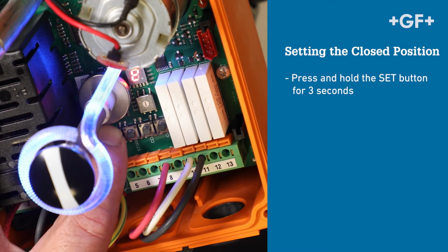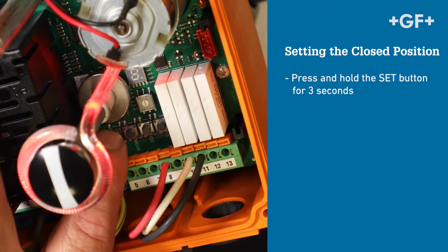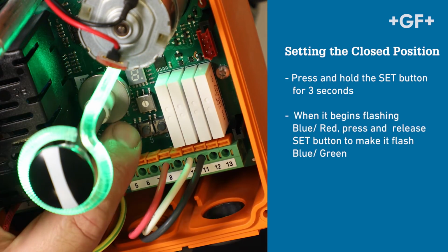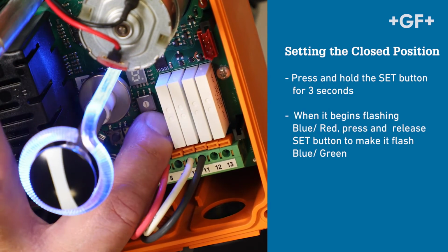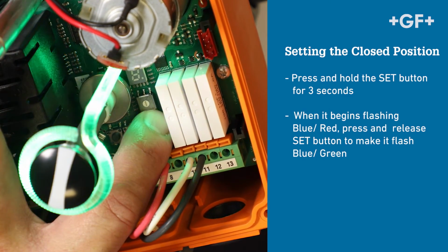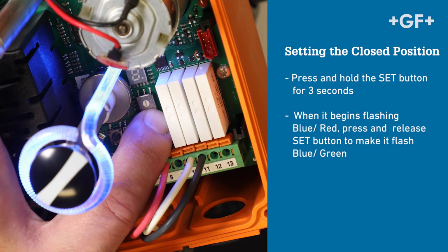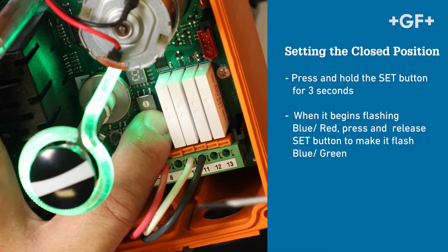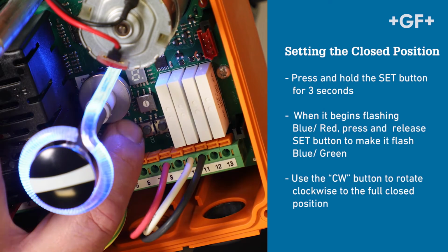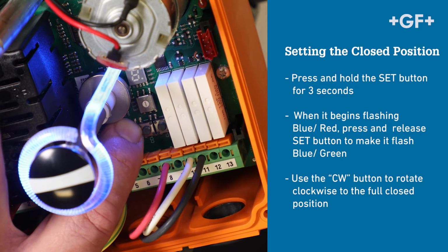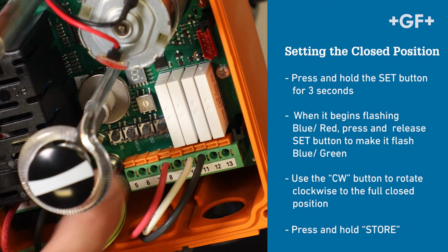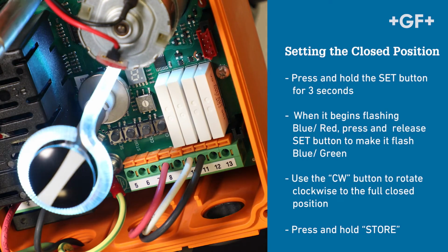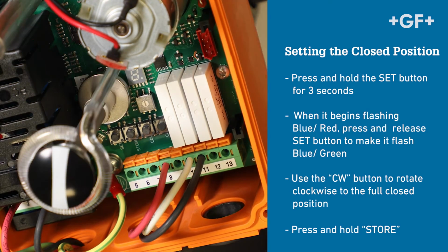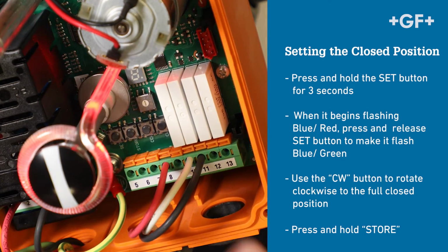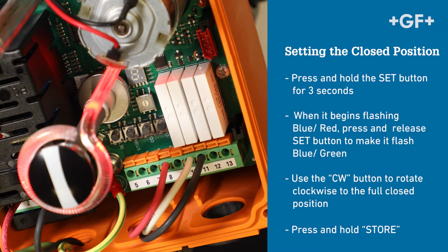To set the closed position, press and hold the Set button for 3 seconds. When it begins flashing blue and red, press and release it to change it to a flashing blue and green. While it's flashing blue and green, use the CW button to rotate the actuator to the full closed position. Then, press and hold Store. Currently, we have power to terminal 1, so the actuator is rotating back to the open position.